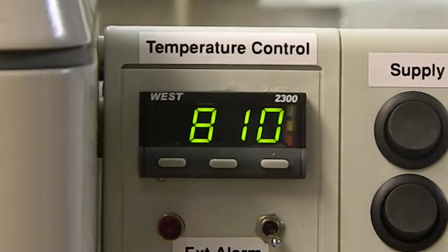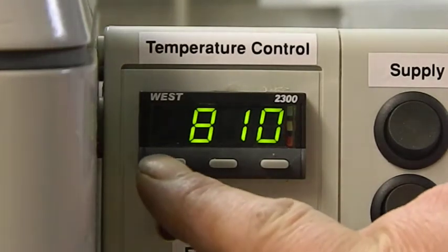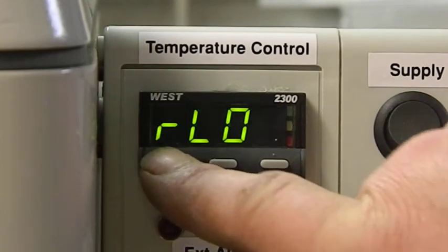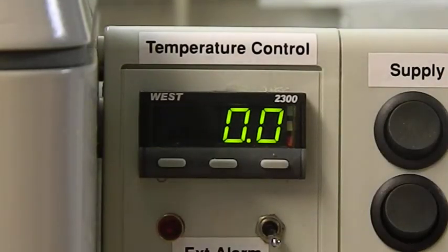SENS is the parameter for the sensor, so it tells the controller what type of sensor is fitted. This particular machine has a PT100 Class A sensor and the parameter for that is 810. Okay, to move to the next parameter you press the left hand button twice. RLO, this is the minimum set point that the machine will accept, so if you're trying to run the machine below 0 it will not accept the setting.